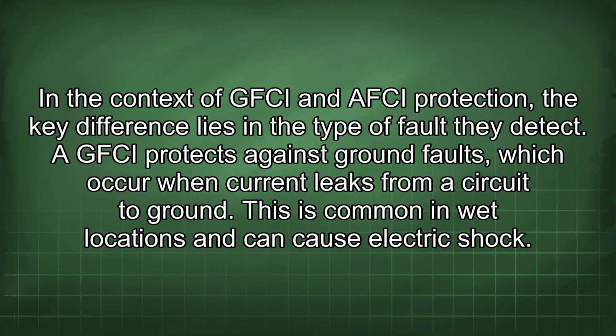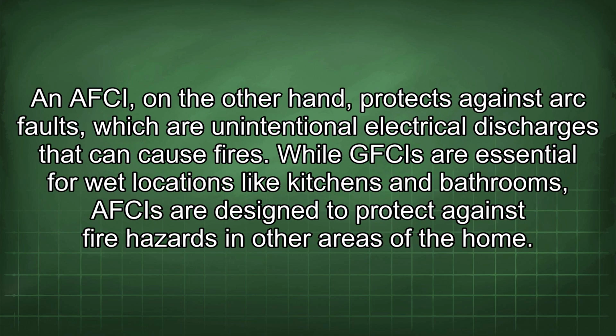In the context of GFCI and AFCI protection, the key difference lies in the type of fault they detect. A GFCI protects against ground faults, which occur when current leaks from a circuit to ground. This is common in wet locations and can cause electric shock. An AFCI, on the other hand, protects against arc faults, which are unintentional electrical discharges that can cause fires. While GFCIs are essential for wet locations like kitchens and bathrooms, AFCIs are designed to protect against fire hazards in other areas of the home.